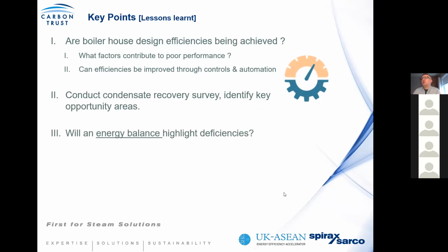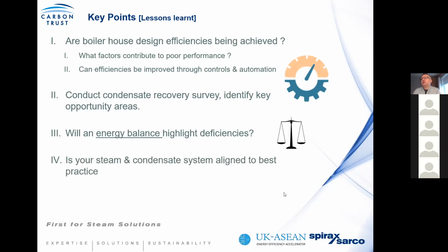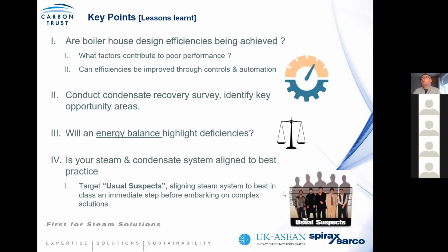Okay, the audit. Will your audit identify deficiencies? Most likely it will, because our experience has shown, even for large multinational companies, there are a lot of deficiencies in the system, which means there's good opportunity for improvement. Again, what you need to understand is whether your steam system is aligned to best practice. And what we say is target the usual suspects. So start off with the simple engineering. Look at the trapping, look at the insulation, look at how you operate steam, look at the feed water system. Use your own system findings to indicate what you need to do. So in other words, the water quality, for example. Don't rush into heat recovery, act on the simple fundamentals first, and then when you've exhausted them, look at the heat recovery.